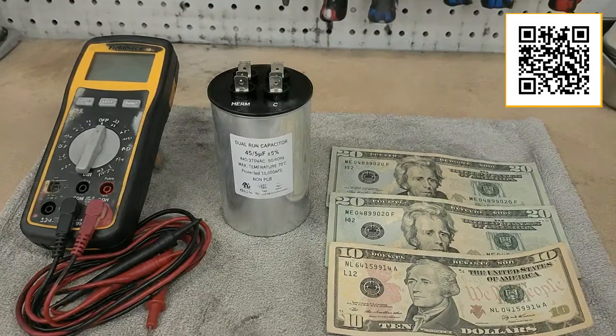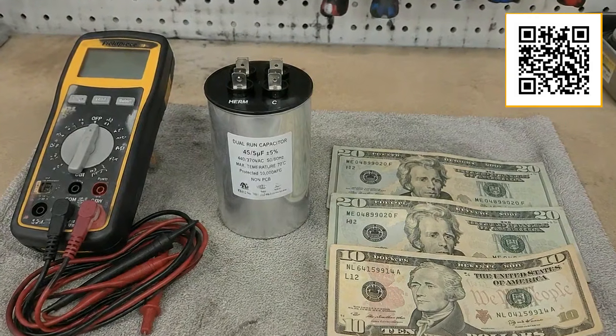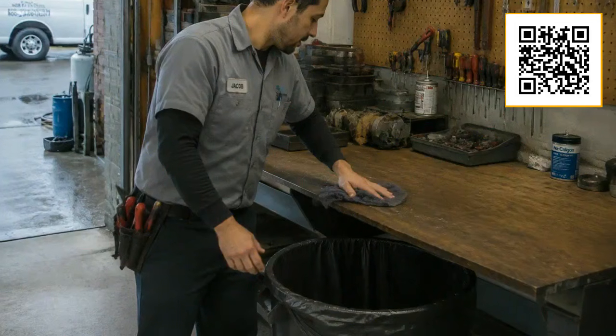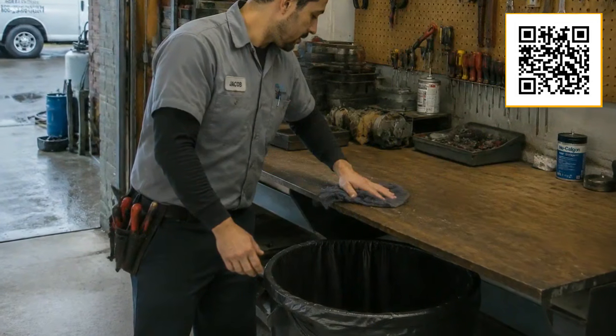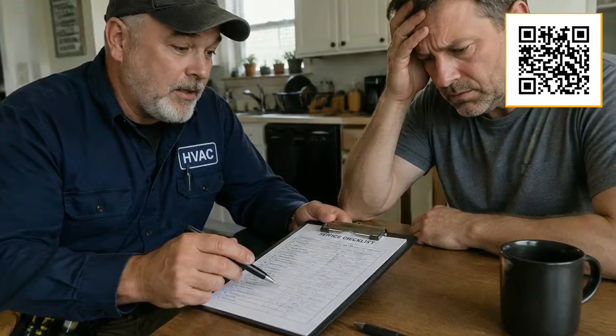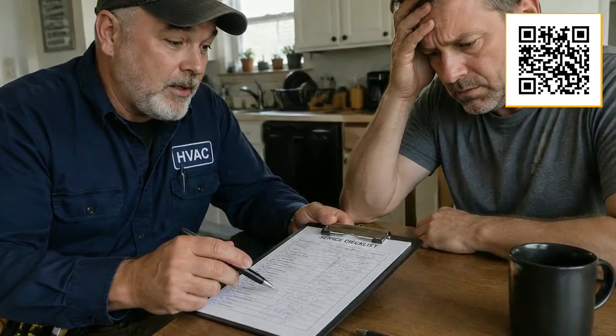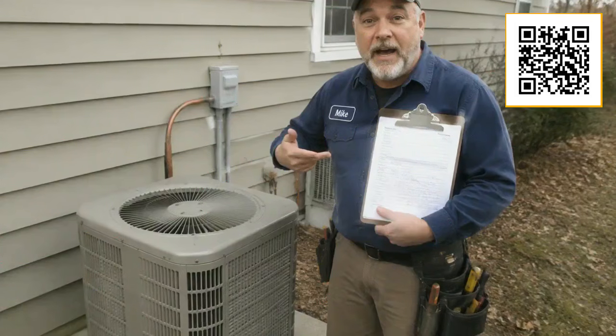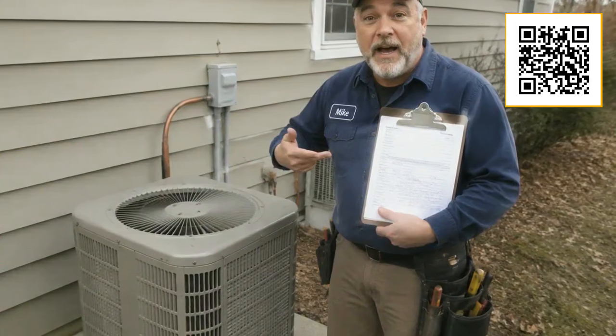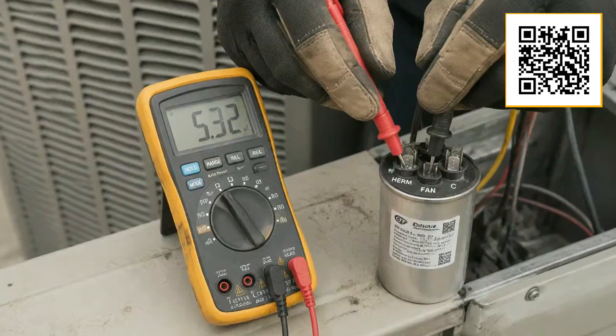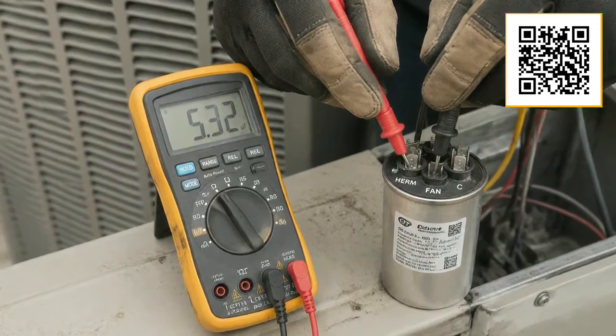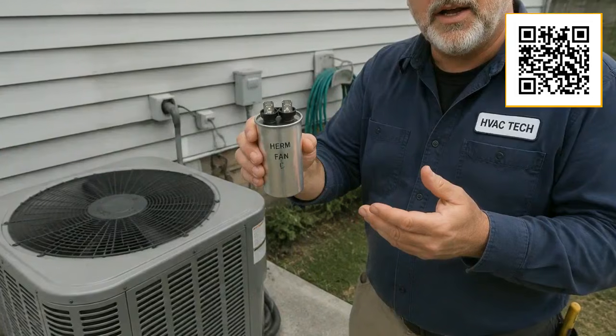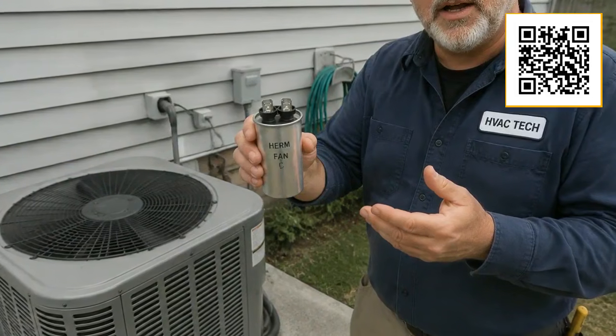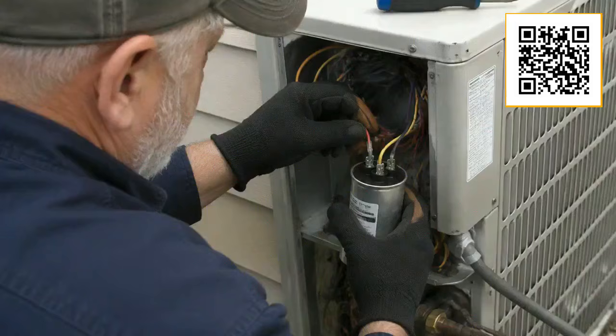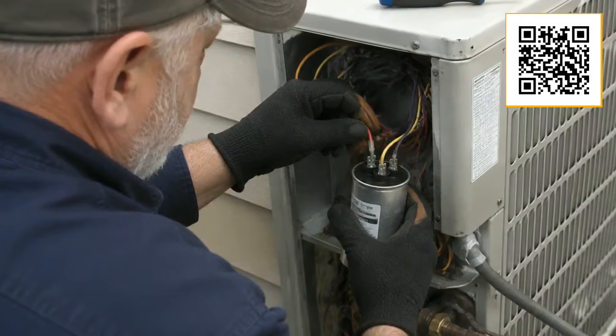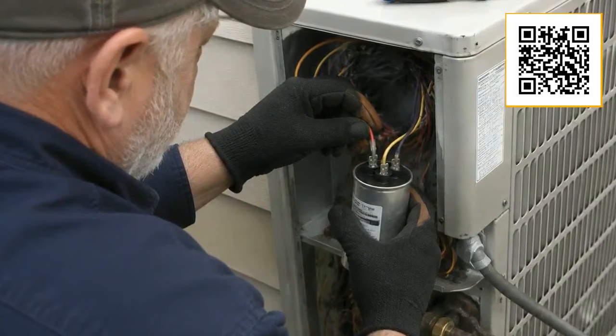A worn capacitor might cost $30 or $40 to replace. If it fails completely and takes the motor or compressor with it, you are looking at hundreds or potentially thousands of dollars. A good technician checks capacitor health during every annual service call, and that test takes about 2 minutes with a basic meter. If your annual service does not include a capacitor check, ask for it specifically. It is one of those small preventive steps that genuinely pays for itself.